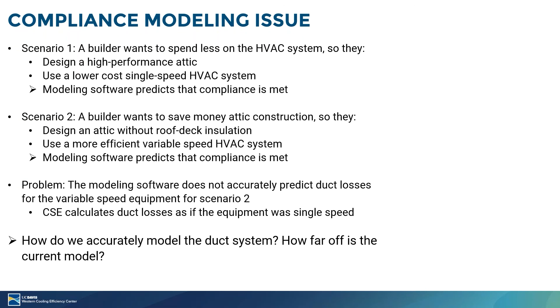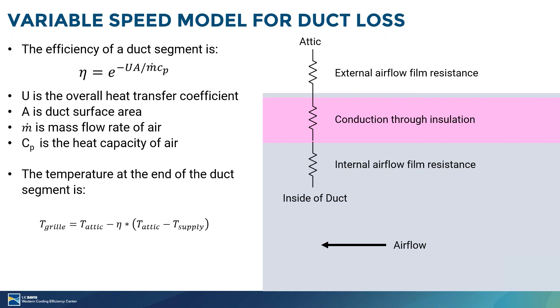to use a sort of a model based on a heat exchanger, we're going to talk about the duct system as having an efficiency. So it's got an overall heat transfer coefficient that includes the external airflow film resistance, the conduction through the insulation, and the internal airflow film resistance. It's going to depend on the duct surface area, the mass flow rate of the air, which is going to change depending on if you're running your variable speed equipment at a high speed or a low speed or whatever it's doing for you. And as a result, we can get the temperature at the end of the duct. And from that, we can calculate delivery effectiveness.